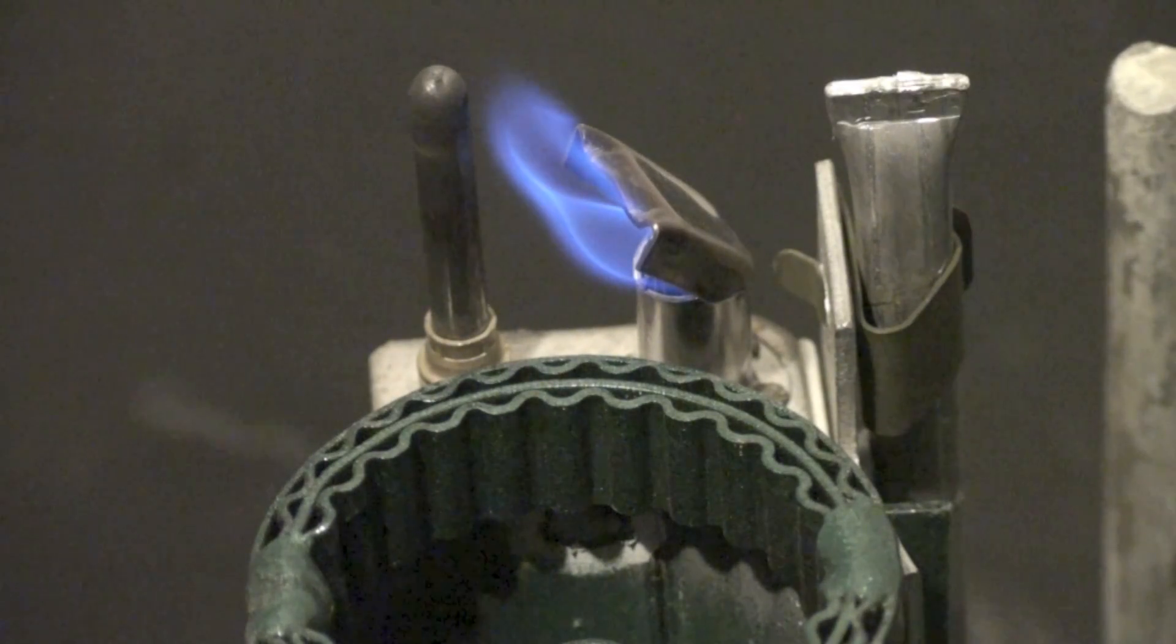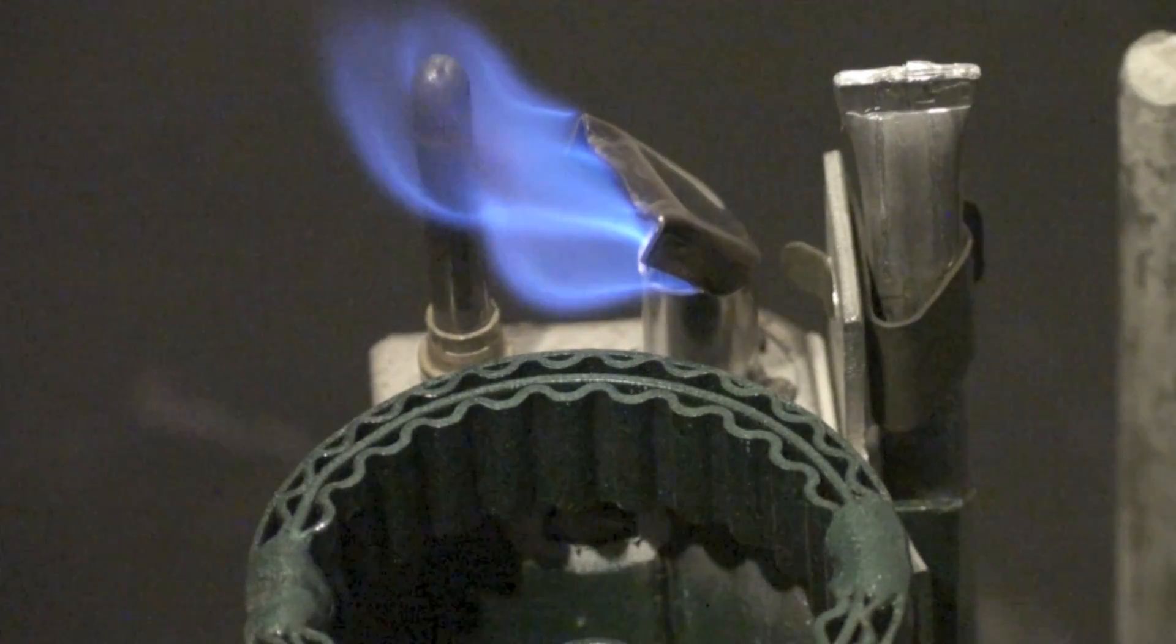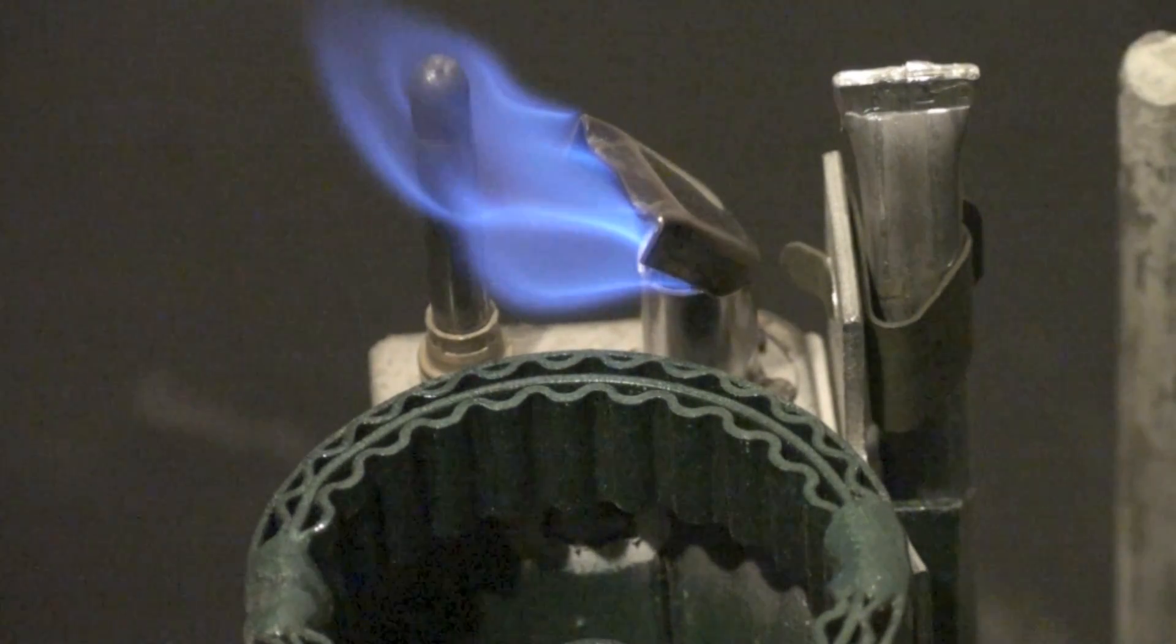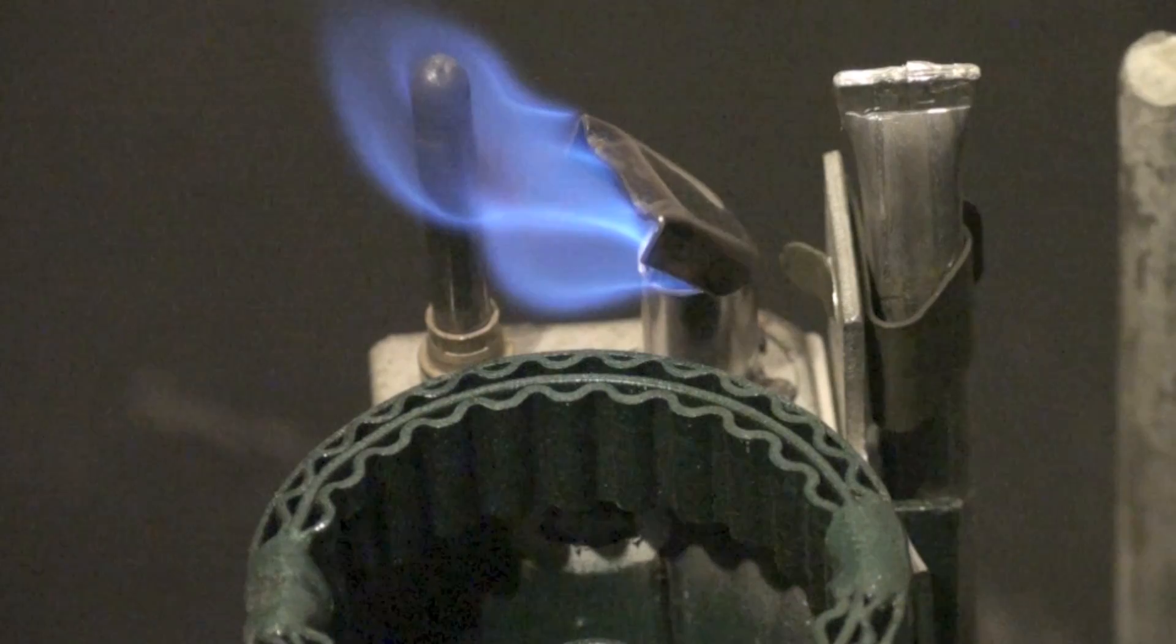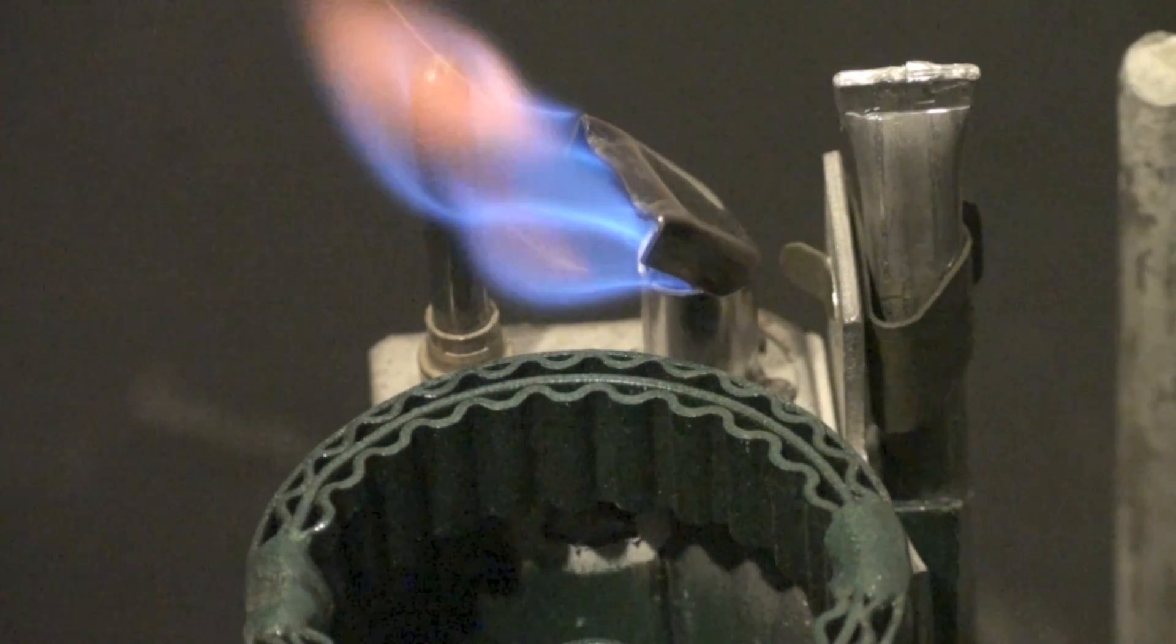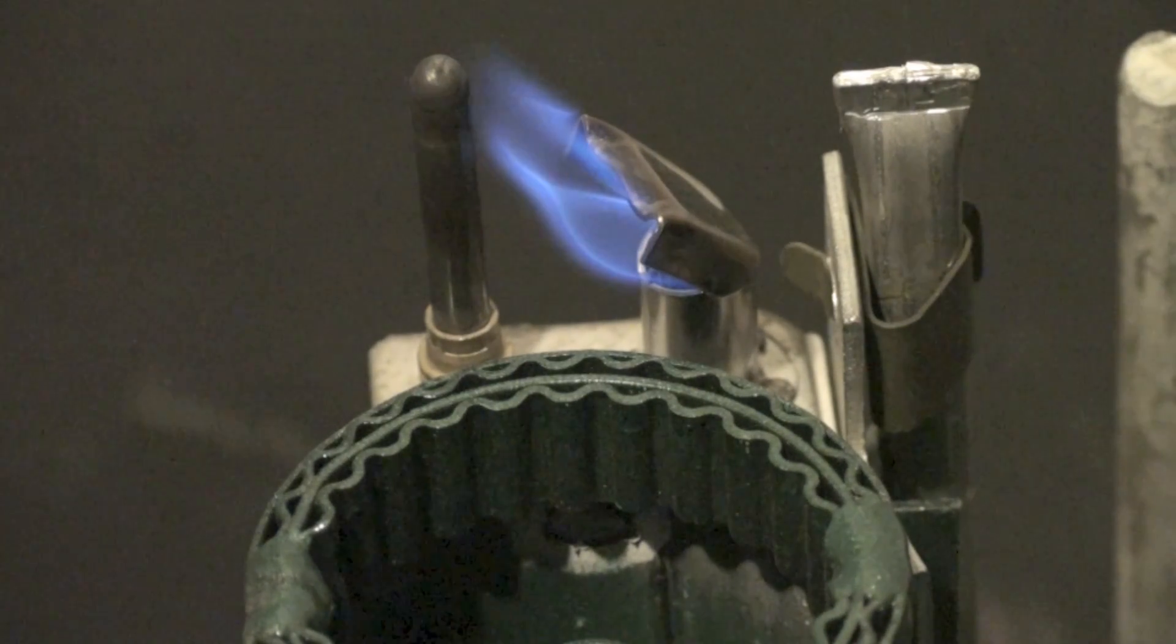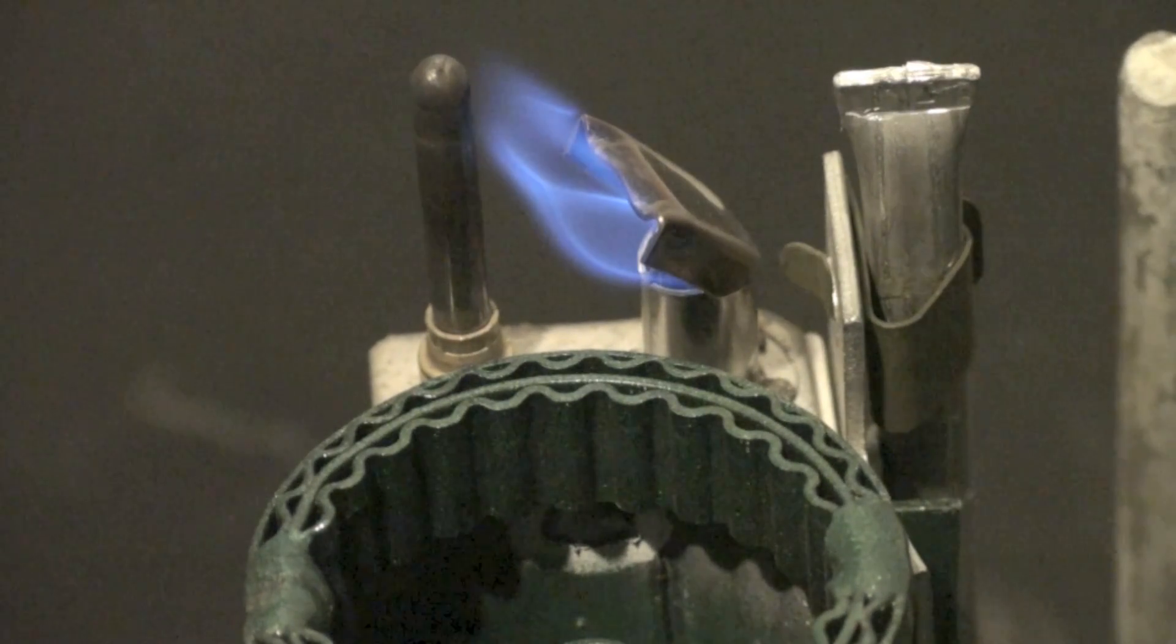Okay, now you can see that pilot's too small. As you bring it back up, now you've got good coverage of the thermocouple. Generally, when you find one that is similar to the way this one was when it was down here like this, that's usually a plugged orifice.